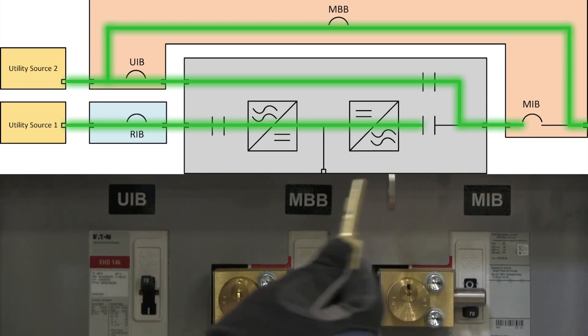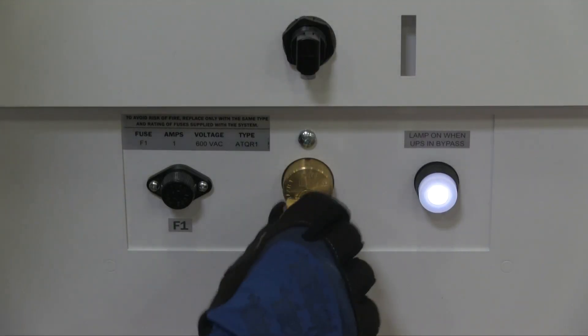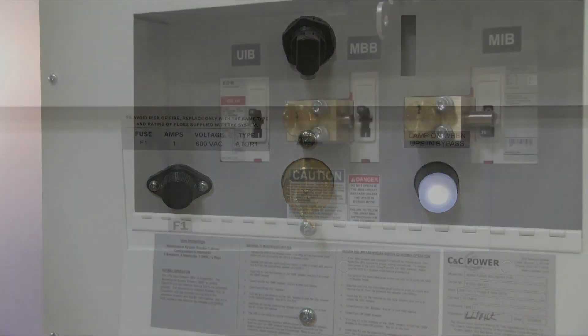Key B1 can now be inserted into the Kirk lock and turned. The UPS is now ready for routine maintenance. You'll notice the key is held captive in the Kirk. This prevents anyone from removing it and changing any of the lock conditions, ensuring safety and system integrity during maintenance.